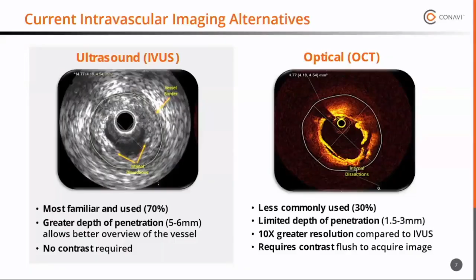So for the other things, they would need to have optical imaging, where it's used in less of the cases, 30%. Has a more limited depth of penetration, but it brings with it 10 times the optical resolution, okay? It does require contrast to flush and acquire the image. So what happens in practice is a doctor will not use two different catheters. They will start and finish with the same image guiding catheter.